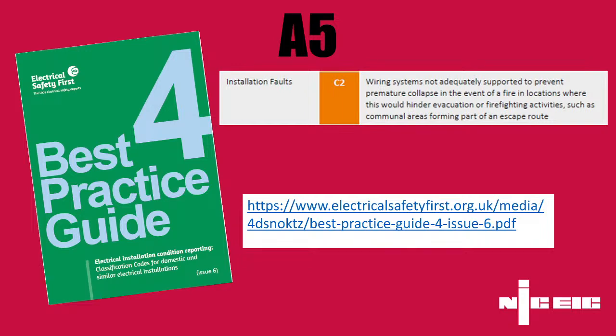It's a lovely document. It's really handy for people to utilise when they're conducting EICRs and giving industry guidance in relation to the coding. It is stated in there that C2 is an appropriate code for that particular installation and circumstance.